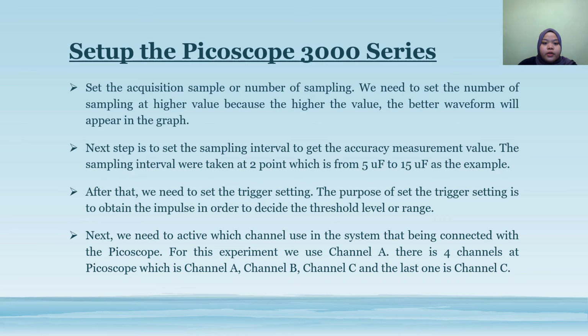After that, we need to set the trigger setting. The purpose of the trigger setting is to obtain the impulse in order to decide the threshold level or range. Next, we need to activate which channel we use in the system that is connected with the Picoscope.